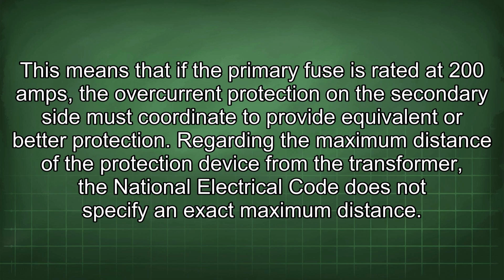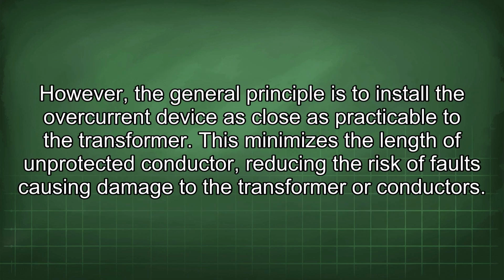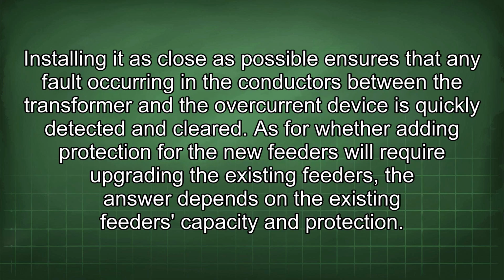Regarding the maximum distance of the protection device from the transformer, the National Electrical Code does not specify an exact maximum distance. However, the general principle is to install the overcurrent device as close as practicable to the transformer. This minimizes the length of unprotected conductor, reducing the risk of faults causing damage to the transformer or conductors. Installing it as close as possible ensures that any fault occurring in the conductors between the transformer and the overcurrent device is quickly detected and cleared.